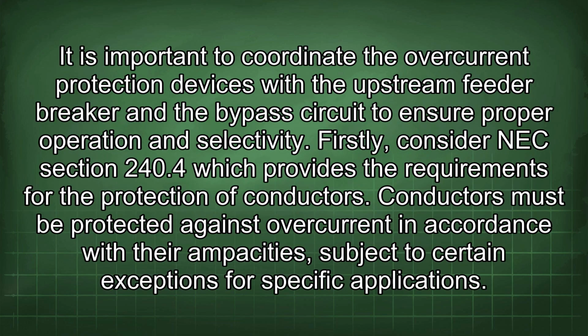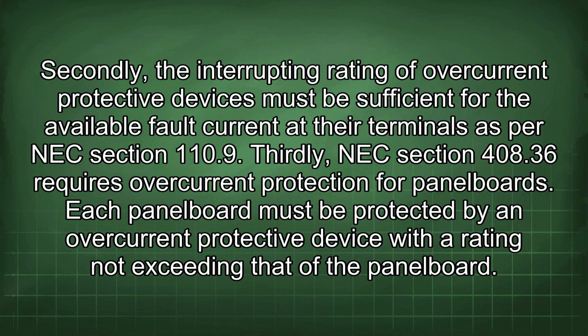It is important to coordinate the overcurrent protection devices with the upstream feeder breaker and the bypass circuit to ensure proper operation and selectivity. Firstly, consider NEC Section 240.4, which provides the requirements for the protection of conductors. Conductors must be protected against overcurrent in accordance with their ampacities, subject to certain exceptions for specific applications. Secondly, the interrupting rating of overcurrent protective devices must be sufficient for the available fault current at their terminals as per NEC Section 110.9. Thirdly, NEC Section 408.36 requires overcurrent protection for panel boards. Each panel board must be protected by an overcurrent protective device with a rating not exceeding that of the panel board.